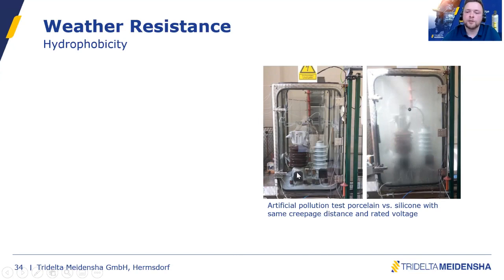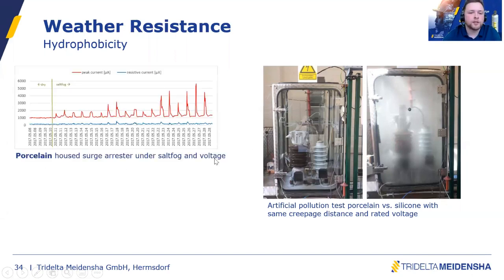And on the bottom, you see our smart count device connected. So it will record the leakage current and the surface current of the surge arrestor. And then the test started and salt fog is injected into the chamber here on the right picture. And you will see on this diagram here on the left side the behavior of the current of the porcelain housed surge arrestor. We have this area before this green bar. It's the condition before the test starts. So we have 1 milliamp total current flowing, very stable.